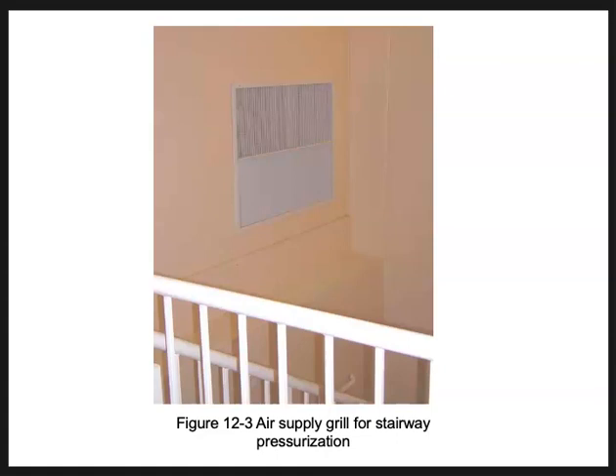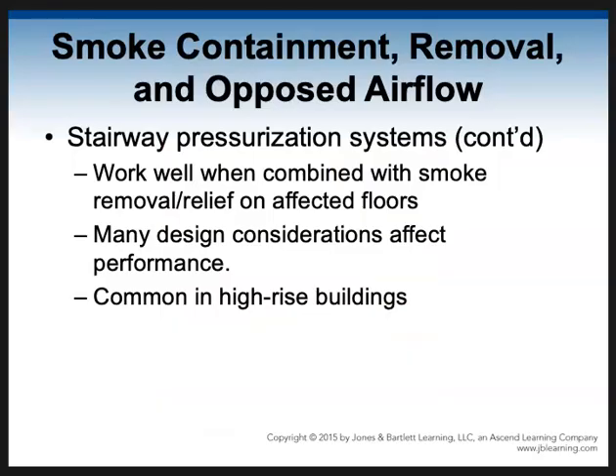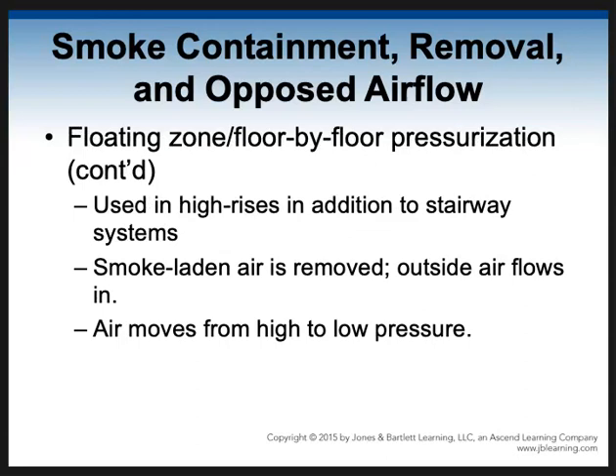them. Now, they've got to make sure the door closes behind them, and usually that's done automatically with the door. It will force it closed, but if it doesn't, the people need to close it. So keep that smoke out. They work well when combined with smoke removal or smoke relief on the affected floors, where other kinds of fans are pulling the air out instead of pushing air in, and they're pulling the air out of the smoke floors to evacuate the smoke. So all these different things have to be considered by the engineer when they're making them, and they're very common in high-rise.